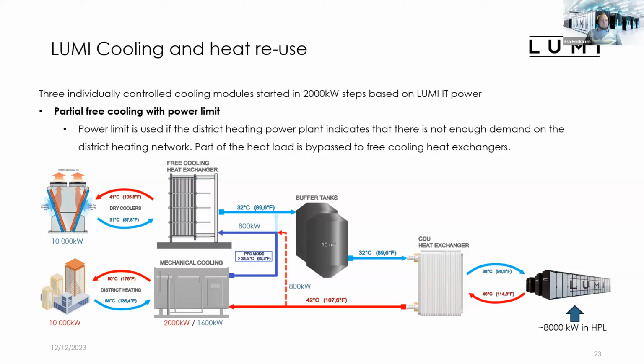And this applies basically in the beginning of the heating season and at the end of the heating season. So usually in the spring and in the fall, when the daytime temperatures increase too much and heat load demand is too low to put all the heat to the district heating network. And this is because the power plant in the area has its minimum operational power, which it cannot go underneath. So they need to make sure that we are not putting out district heating if they are closing in on this minimum operational level of the district heating power plant in the area.